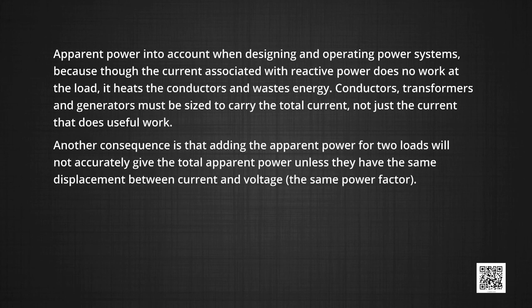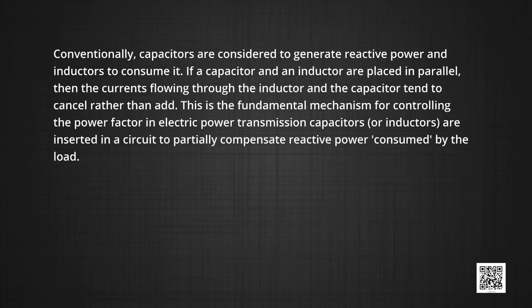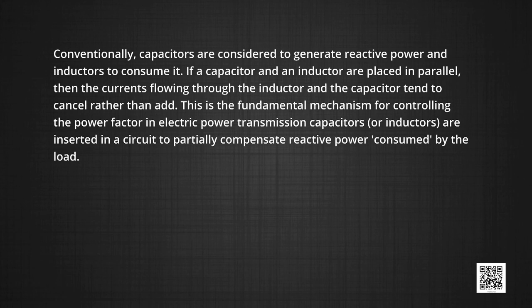Adding the apparent power of two loads will not accurately give the total apparent power unless they have the same displacement between current and voltage — that is, the same power factor. Conventionally, capacitors are considered to generate reactive power and inductors to consume it. If a capacitor and an inductor are placed in parallel, the currents flowing through them tend to cancel rather than add. This is the fundamental mechanism for controlling the power factor in electric power transmission. Capacitors or inductors are inserted in a circuit to partially compensate for the reactive power consumed by the load.